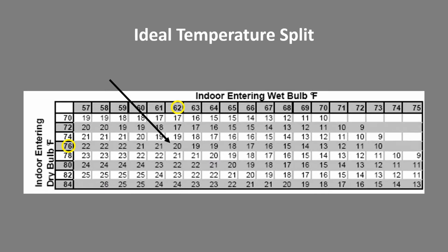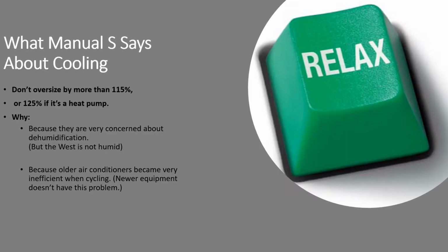But that's to say, some days we get out there and it's kind of muggy, and it's actually a 68 degree entering wet bulb, and we have a 72 entering dry bulb. Our sensible split would only be 13 degrees. What's happening here is you're releasing quite a bit of energy when you turn all that water vapor back into liquid, and that lowers your sensible capacity. But Manual S says about cooling, don't oversize by more than 115%, or 125% if it's a heat pump. We don't have to worry about that oversizing of air conditioner too much.